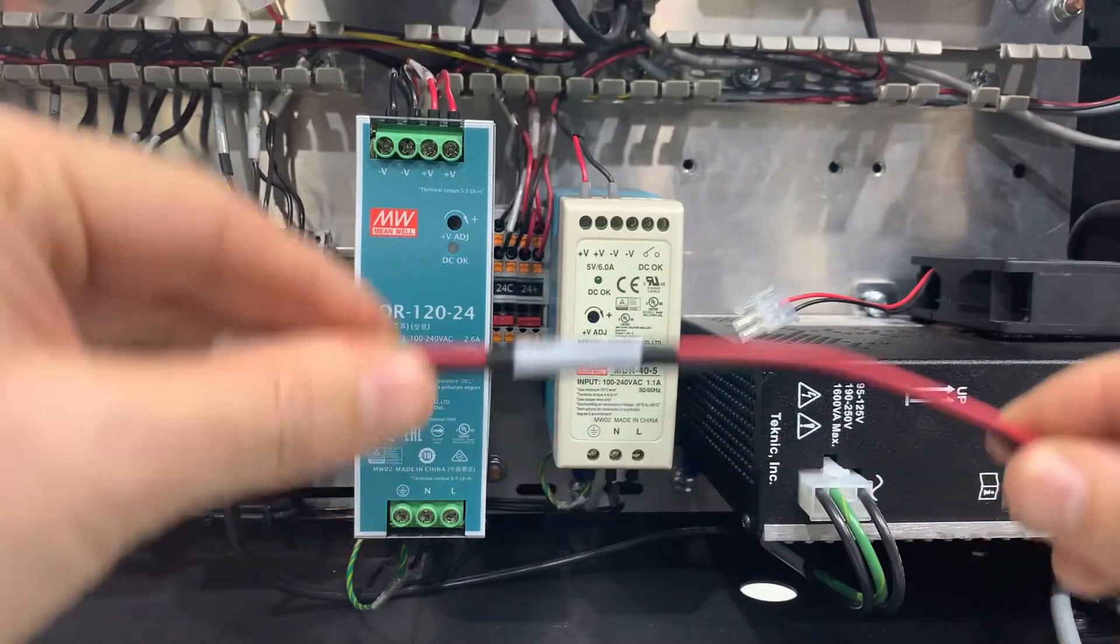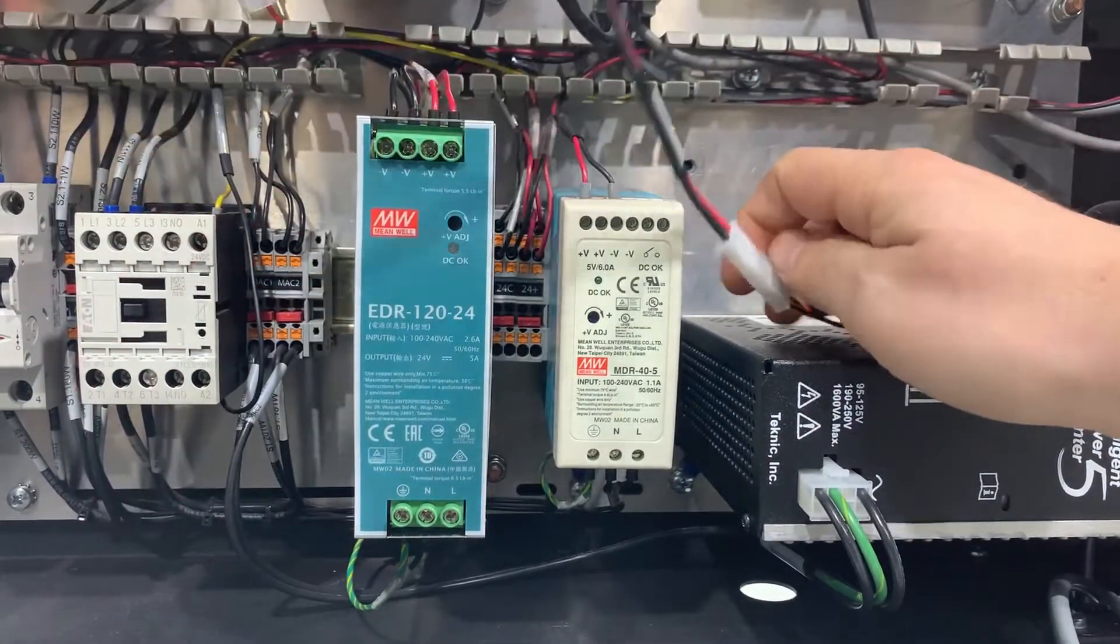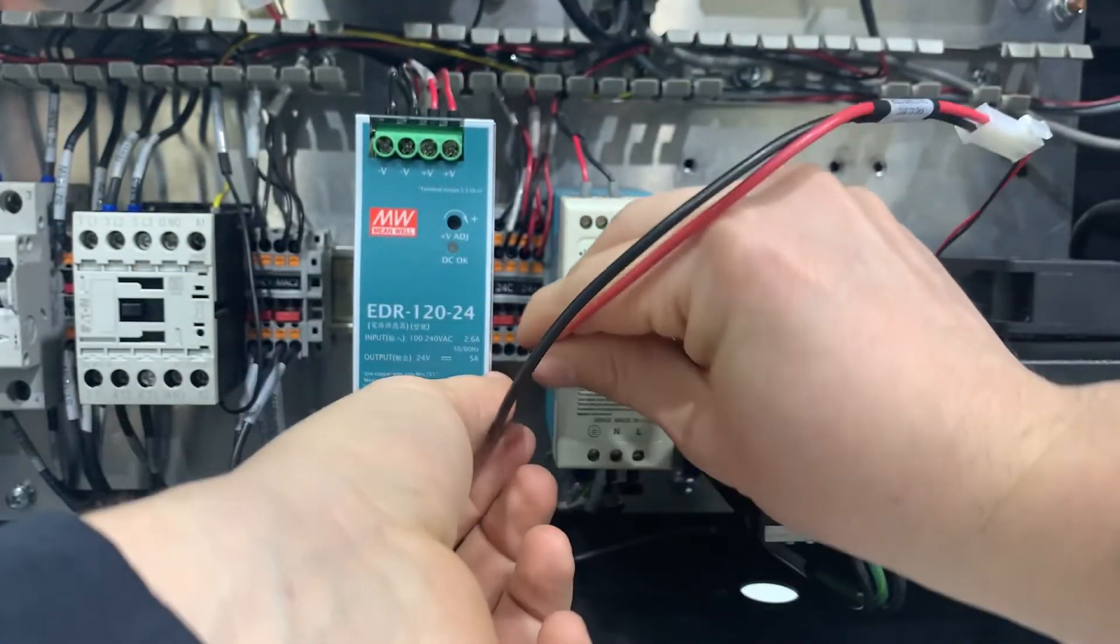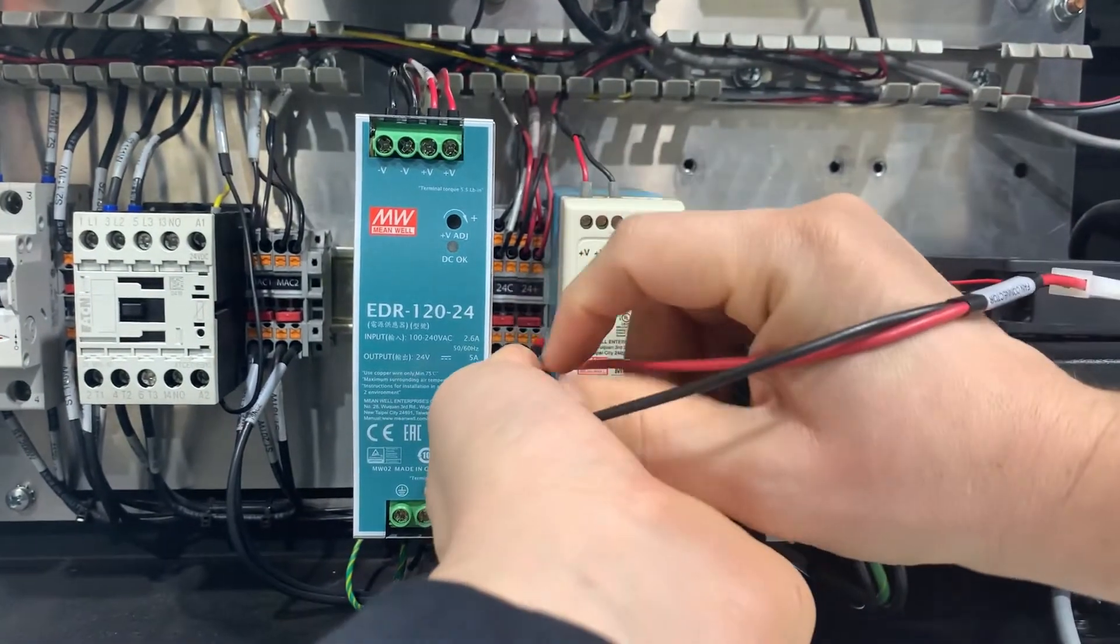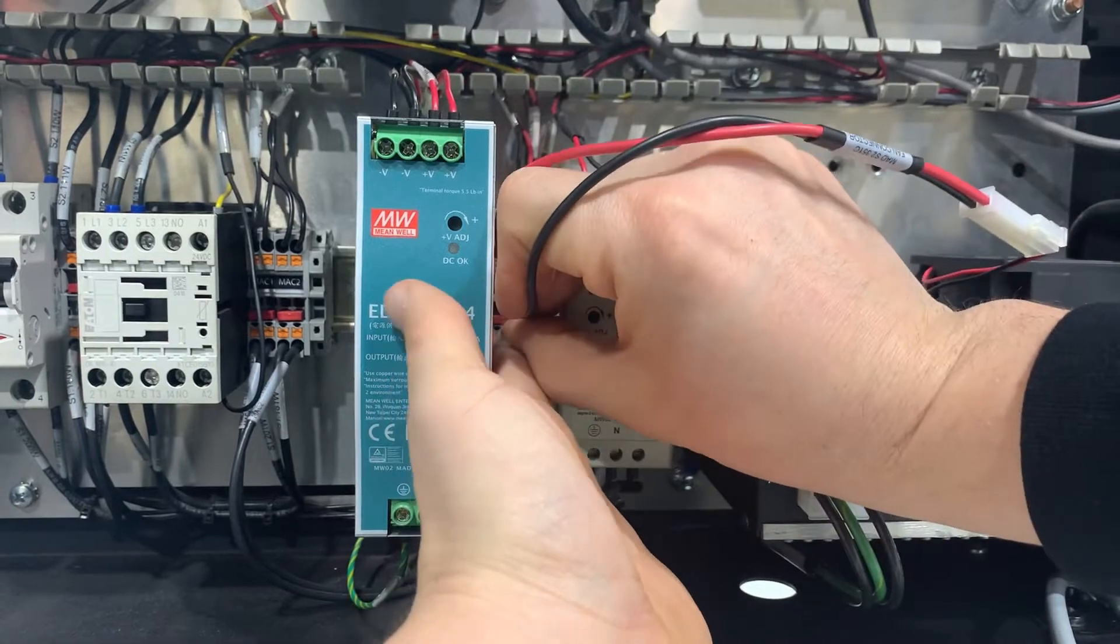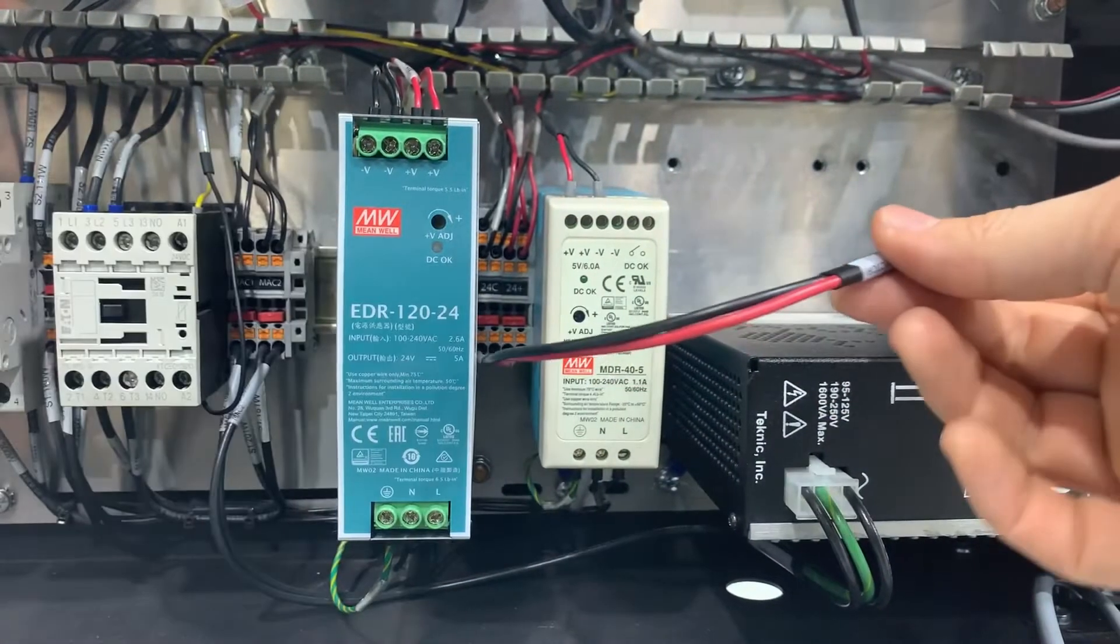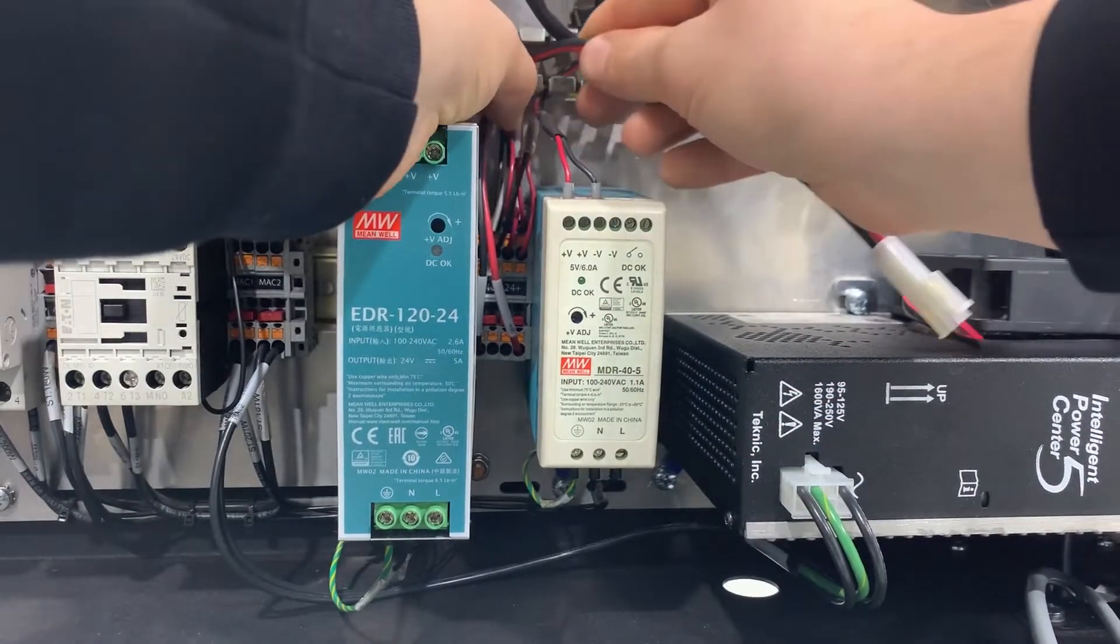Next, install the fan power cable. Connect the white end of the cable to the plug on the fan. Insert the red 24 volt plus and black 24 volt common cables into their matching locations in the terminal block. It is a tight fit and I cannot fit my hands in there, but by grabbing the cable a few inches back I am able to push it into the spring cage without removing the power supplies. Finally, route the fan connector up into the horizontal wire duct and back over and down next to the low voltage power supply.